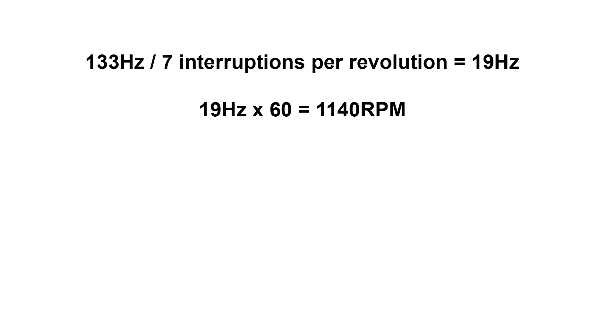Since there are 60 seconds in a minute, if you multiply the frequency in Hz by 60, you get the rotations per minute. So 19 Hz times 60 tells us that this fan is rotating at 1140 RPM.